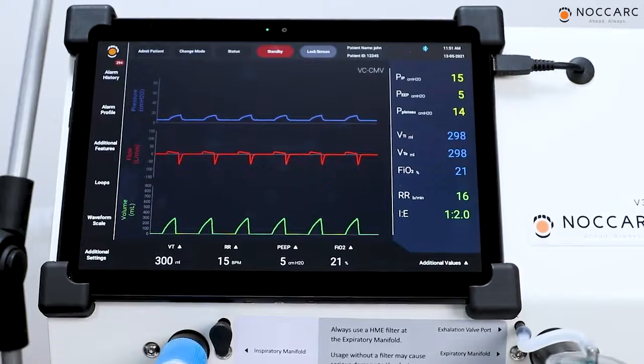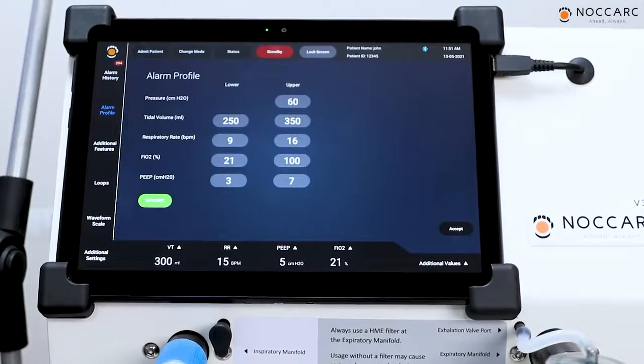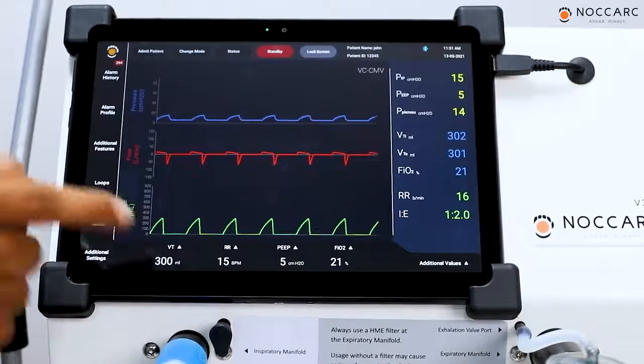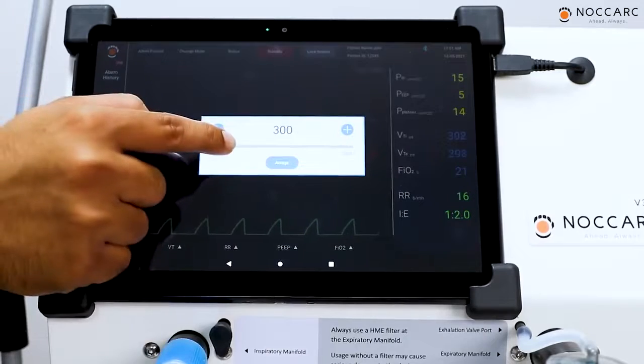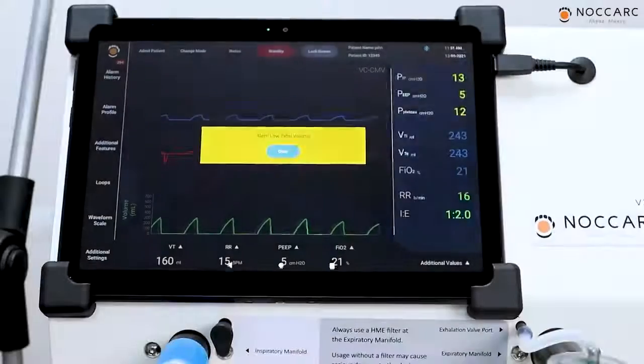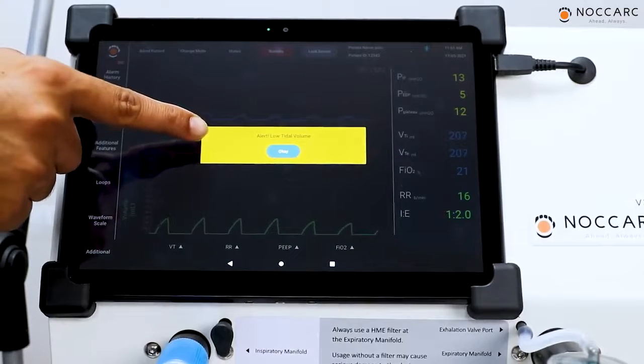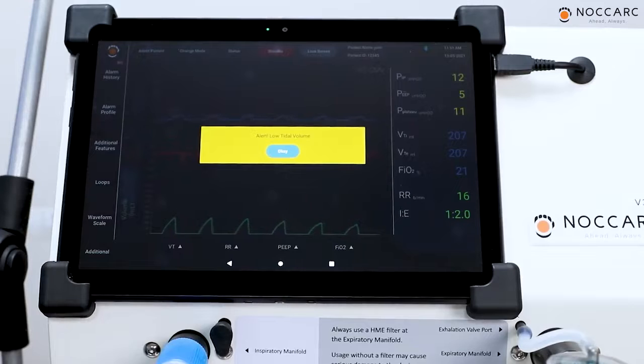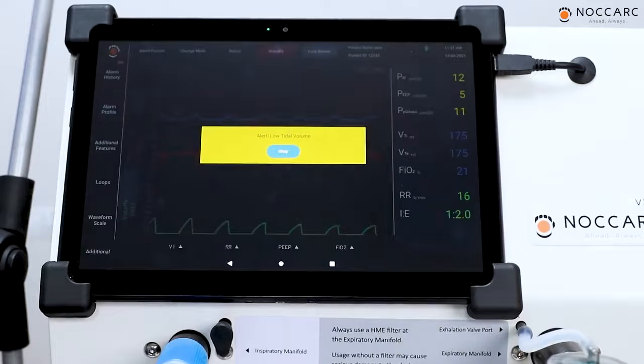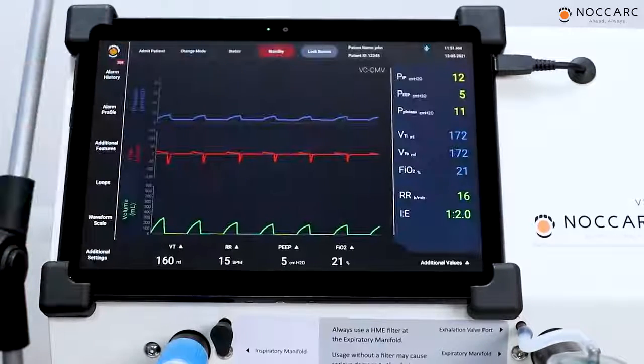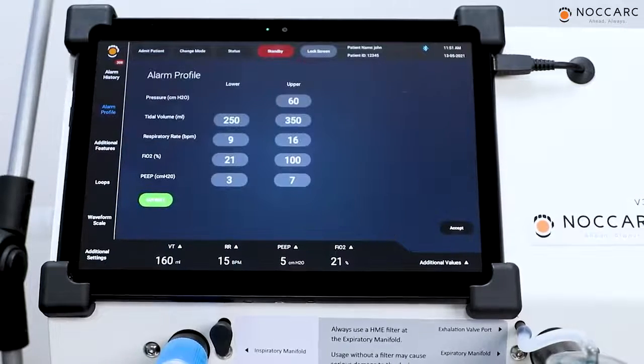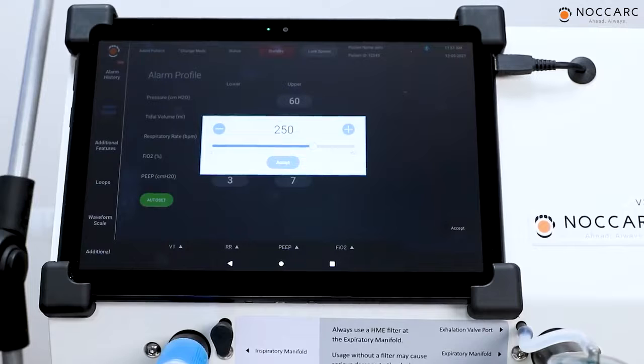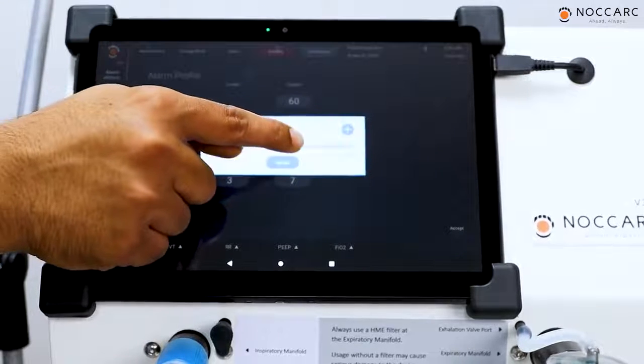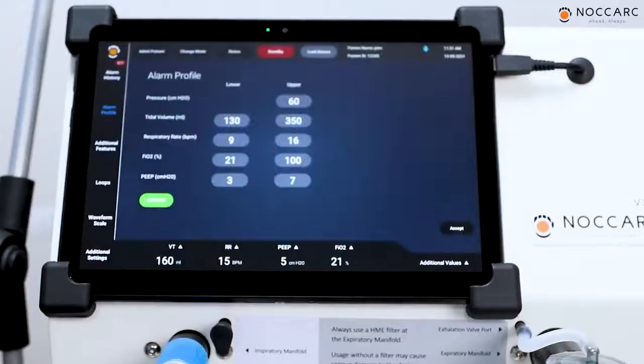To test the alarm, set the ventilation parameters outside the lower and upper bounds of the alarm profile. For example, in the alarm profile, the lower limit for tidal volume is 250. So we will set the tidal volume less than 250. Here you can see a low tidal volume alarm is shown on the screen. That indicates your tidal volume is lower than your alarm profile. To stop this alarm, go in the alarm profile and change the lower limit for tidal volume as per the set volume. Then press accept.